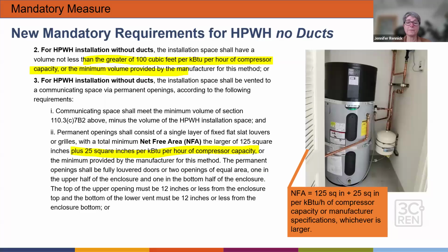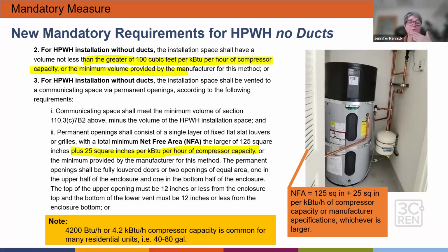And just as a rule of thumb, if you don't know what kind of heat pump you're going to be putting in, architects, you can take a look at this and use 4,200 BTU per hour compressor capacity. It's really a common size, and then you would use that compressor capacity and multiply it times either the 25 square inches per kBTU for your net free ventilation area, or 100 cubic feet times that number for the volume of ventilation that you need.